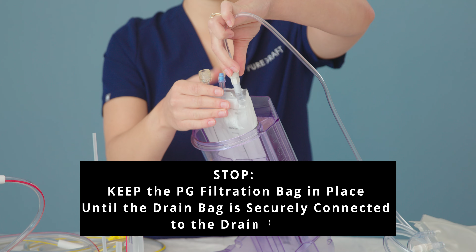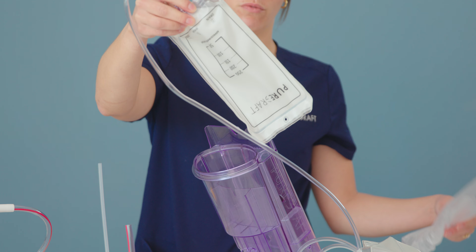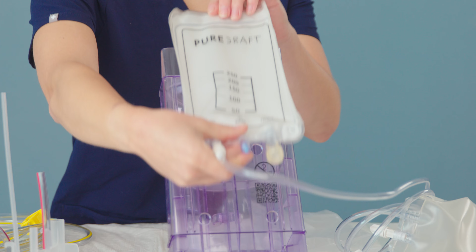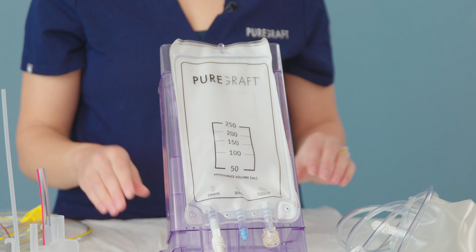Before lifting the Puregraft bag from the sink device, connect the drain bag tube to the drain port. Note that the drain port is open. If the Puregraft bag is inverted before connecting the drain tube, waste fluid from the bag will spill onto your surface. Remove the Puregraft filtration bag from the sink device. The thin plastic liner will allow you to slide the filled Puregraft bag out of the sink device easily. Once the Puregraft bag is removed, you may discard the liner. Hang the Puregraft filtration bag from the hook on the front of the sink device and allow the waste fluid to drain for 1 to 3 minutes.